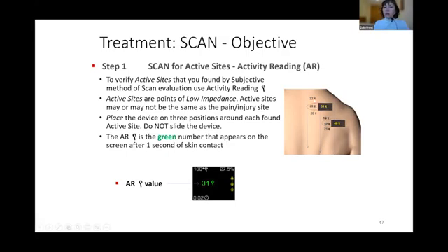So for that reason, within this circle, I just place the device in 3 places. Why 3? It could be 2, but it's easier to discern where the high readings are. So for example, 22, 28, 20, yeah? Of course, 28 is higher.